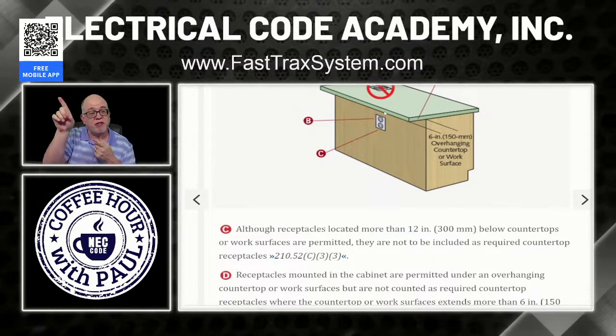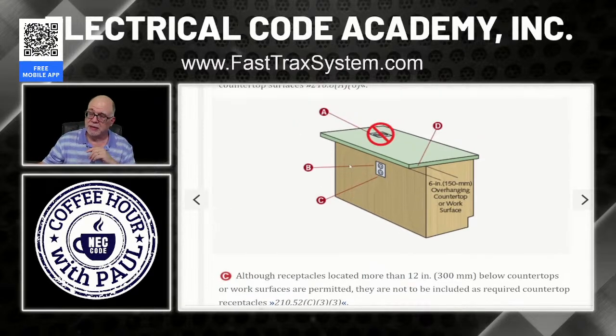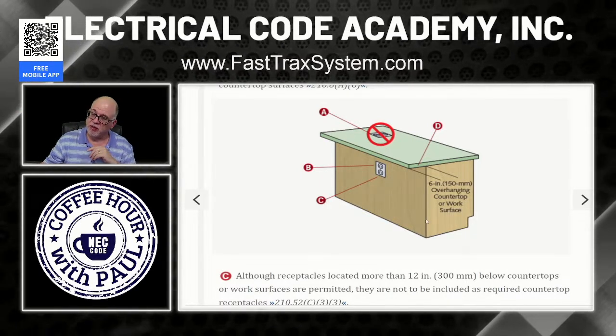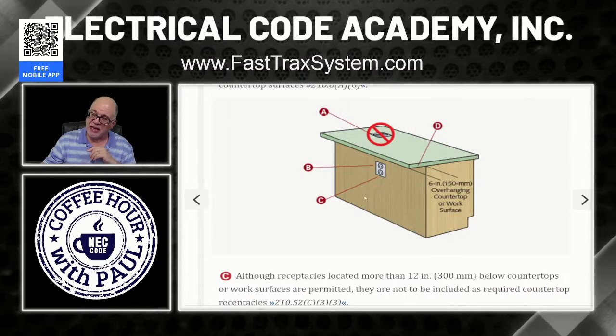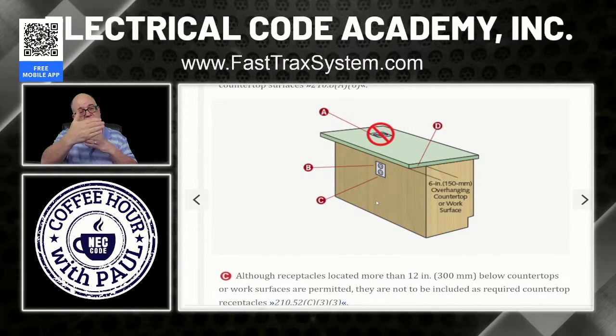At least the one to serve the countertop, I couldn't. Could I put one down here? Maybe this is dividing the living room from the kitchen. Well, then you've got to be really careful, because if this receptacle here is to serve this island, an inspector could consider this a room divider and it could require a receptacle on this side to serve the living room.